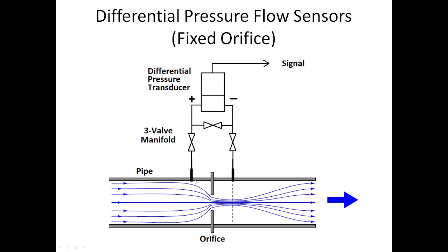So what you do is you create an orifice, and on one side you're going to have pressure built up, and on the other side, as the gases go by, it creates almost like a venturi, and that creates suction, or a very low pressure zone right here. So on this side here, you're going to see the scale go this way, and over here you're going to see pressure build up on this side. The higher the flow, the greater this differential is going to be. This is a fixed orifice flow sensor.